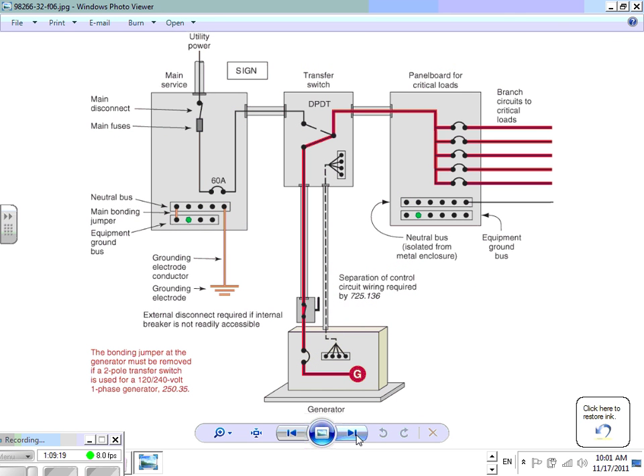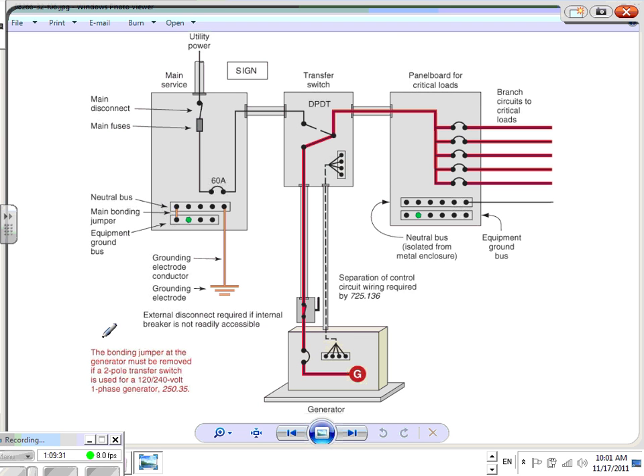Okay. Here's what happens, guys, when I lose power. When I lose power, I transfer myself to the generator. So when I lose power, single phase, the bonding jumper at the generator must be removed if a two-pole transfer switch is used, a two-pole. This is what we said. This is, guys, just to give you an idea if you're running a separately derived system or a non-separately derived system. Any question? Any question? Running on generators?